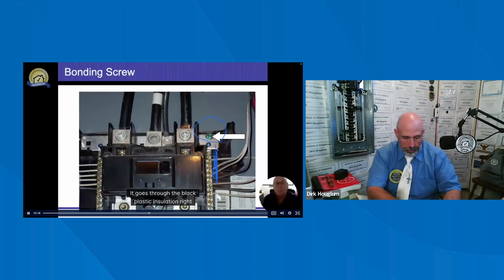It goes through the black plastic insulation right there, and it ties into the metal box that's behind it as well. Now that metal plate runs behind the neutral and the energized conductors, and then it also ties into this neutral bus bar on the left-hand side. That is my bond. So if anything energizes my grounding system, that's going to allow electricity to get over to my neutral system, and then I'm going to have free flow electricity enough to go ahead and trip my breakers. This is known as a bond screw.